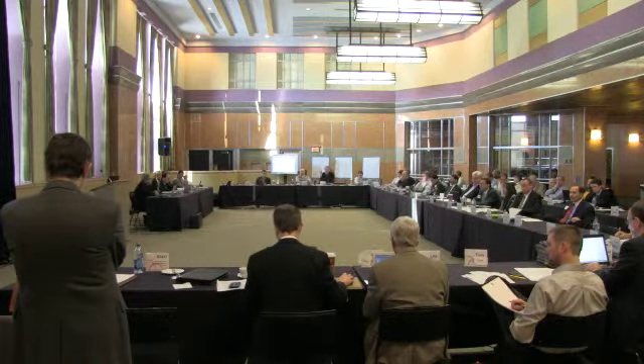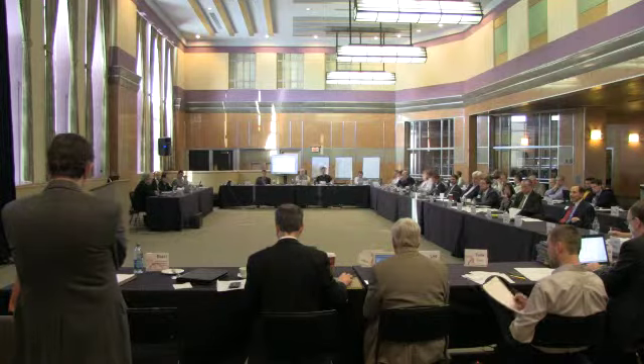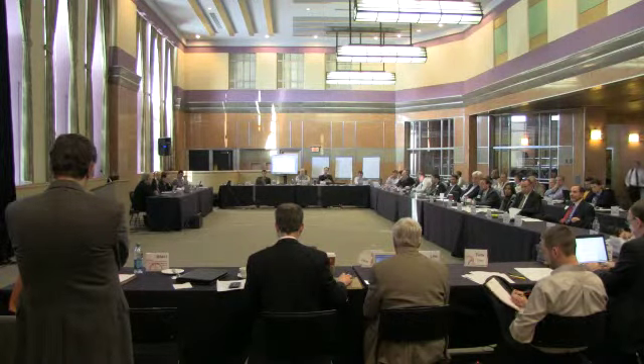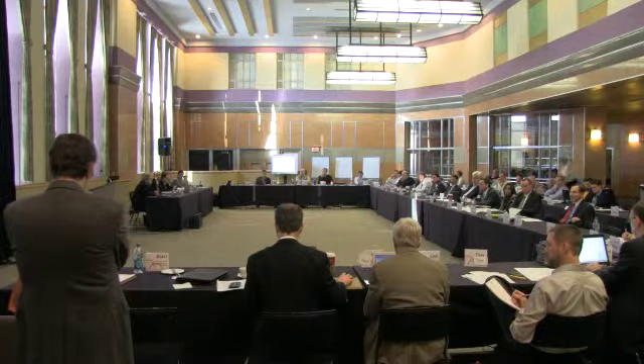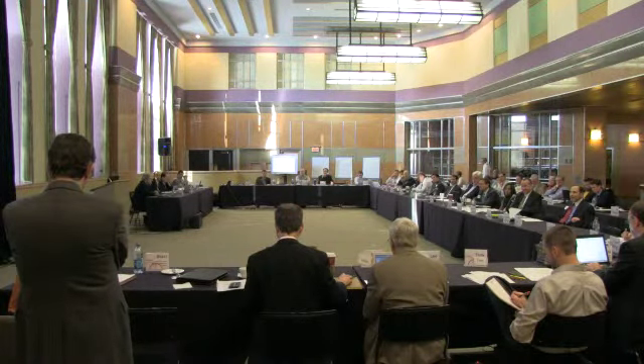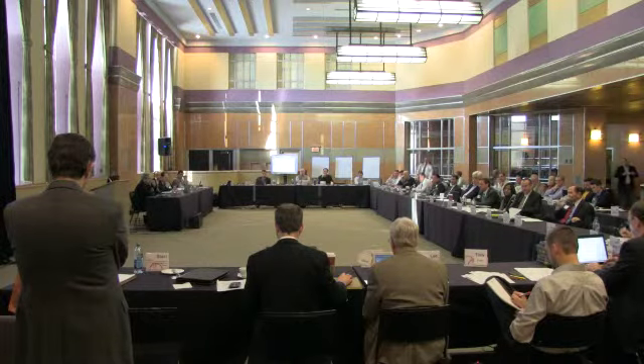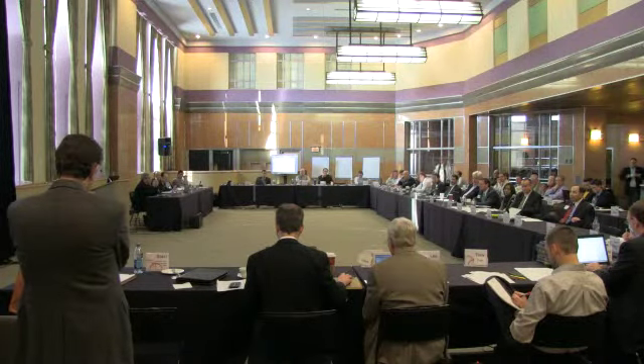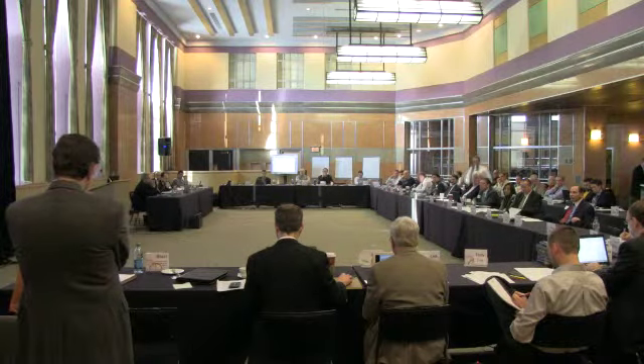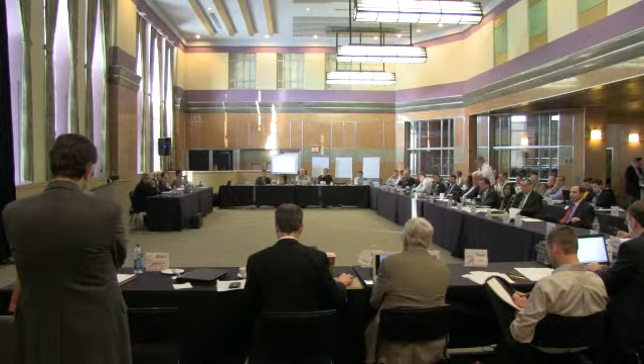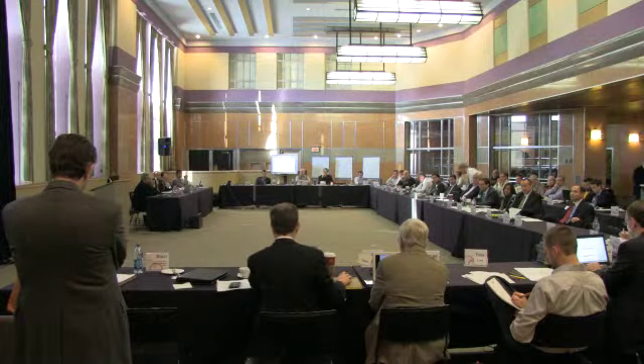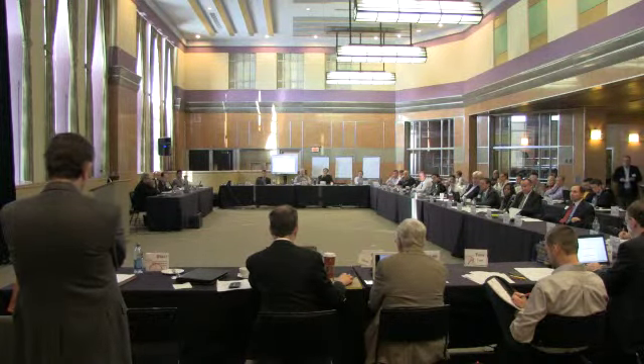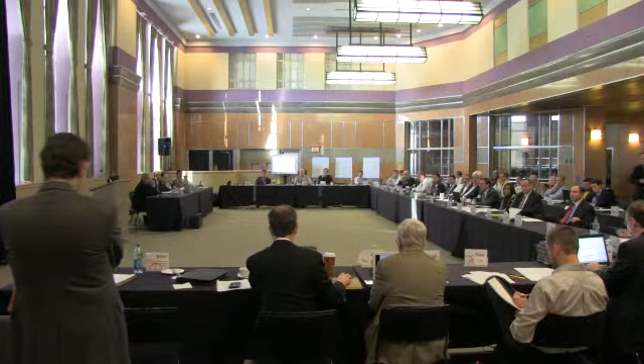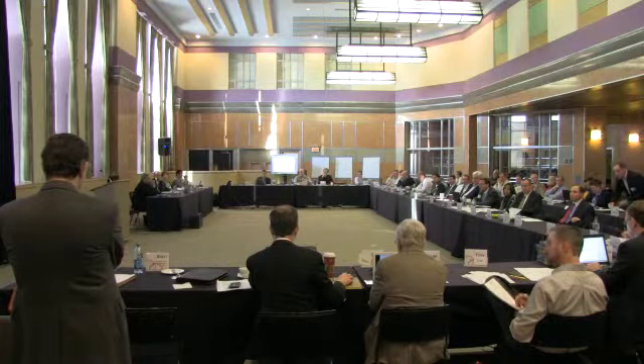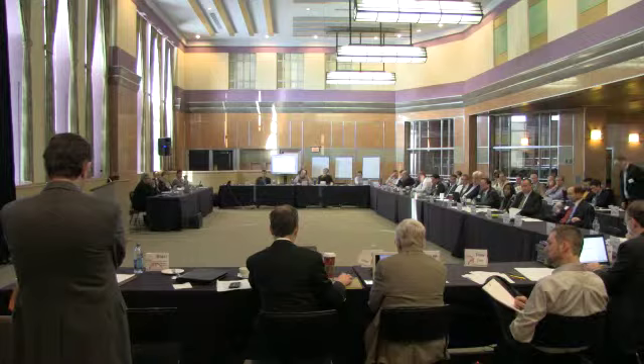The lighting, and the lighting control that Paul touched on earlier, is another issue. Our means of turning lights on and off in this building is to send a person, or more than one, around the building each day, usually a couple hours before we open, to start turning lights on. It's not as simple as flipping a switch in a room, because there are no light switches in a room like this. Usually it means going into an electric room and turning everything on by breaker, which happens a couple hours before we open and gets turned off after we close. It's all very time consuming, and lighting ends up staying on much longer than it needs to.